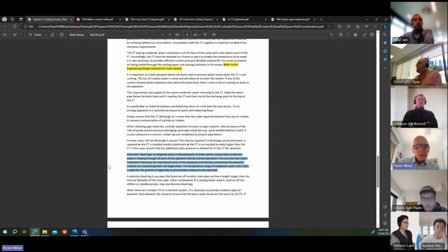Now, you also need to eliminate dead legs. I'll tell you what they are in a second. Or stagnant parts in the pipework. In other words, ensure that condenser water is flowing through all parts of the pipework during normal operation. You want to get the chemicals flowing through the whole system. You don't want parts that... dead leg means there's no water flowing through there.